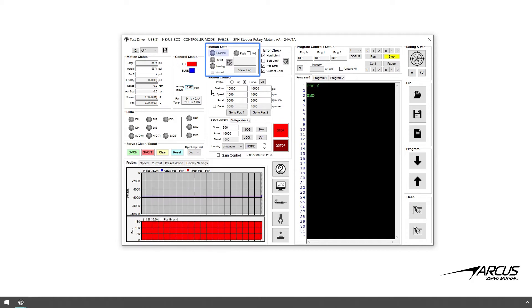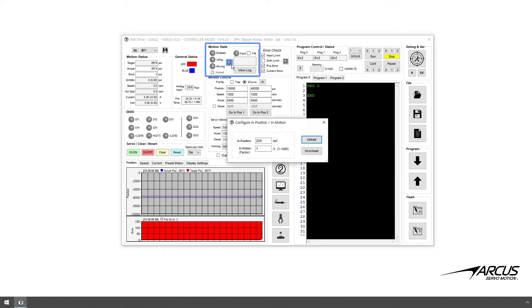Go to the motion state box located on the mid top area. In this box you can see if the motor is enabled or disabled, in position and moving or not. Below is the motor home state — this box will be checked after performing the homing routine successfully. The gear button will open the setup dialog box to set the in-position range and in-motion factor. The in-position range is an encoder count value; with the servo on, the in-position status will be on when the actual position is within the range of the target position. The in-motion factor is used for setting the minimum speed to determine if the motor is moving or not.